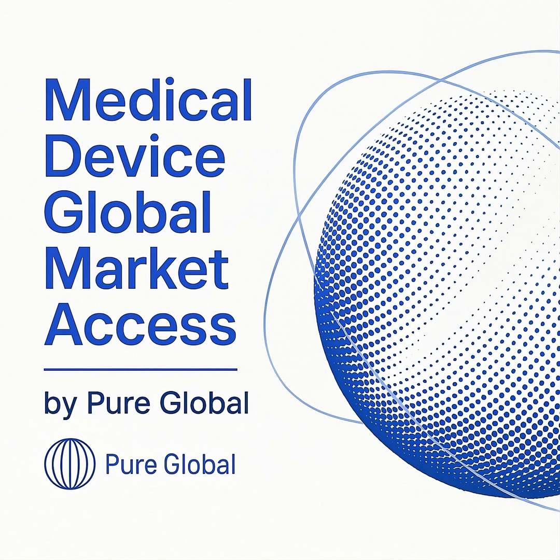The foundation of China's current system is the Provisions for Medical Device Registration and Filing, which became effective on October 1, 2021. This regulation aims to align with international standards, but it codifies several requirements unique to China. The first and most critical step for any foreign manufacturer is appointing a China agent. This local, licensed entity is mandatory and acts as your legal representative, handling all regulatory interactions with the NMPA, from submission to post-market surveillance.